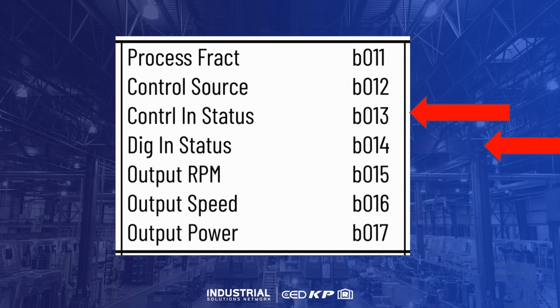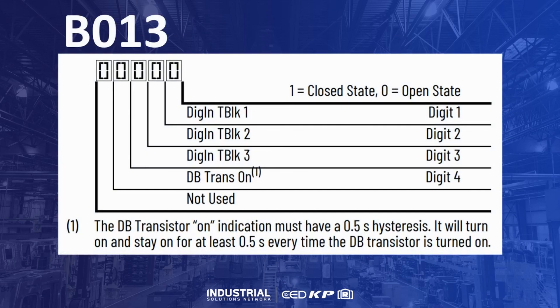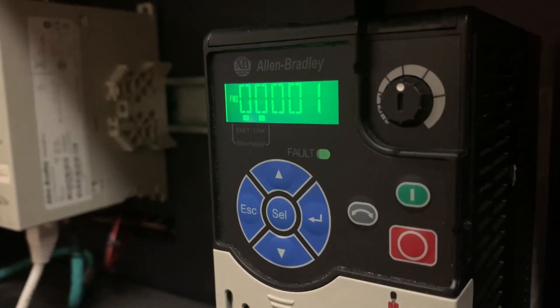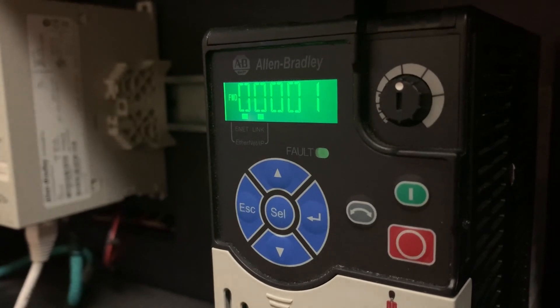Parameters B13 and B14 will display the status of the digital inputs for the drive. Within parameter B13, moving from left to right, the first three digits correspond to terminals 1 through 3 of the drive, respectively. If a 1 is shown, that means the terminal block is receiving a +24 volts DC signal. If a 0 is displayed, then the terminal is not energized.